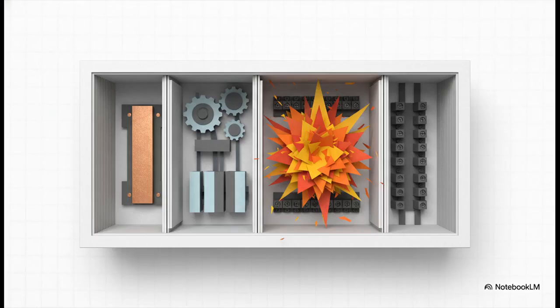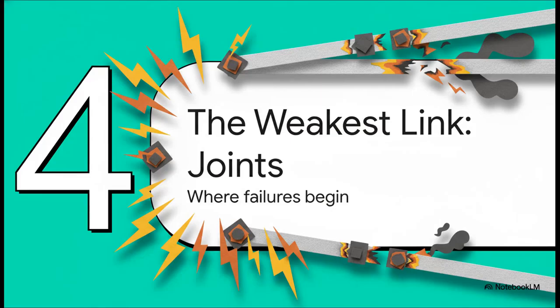Beyond just spacing the bars out, we also have to separate the compartments they sit in. Forms 1 through 4B describe this segregation. Form 4 separation isolates the bus bars, the functional units, and the terminals completely from each other. This radically improves safety for maintenance workers by preventing accidental contact with live parts, and it stops a localized arc flash from spreading like wildfire. But as you might guess, putting in all these physical barriers significantly adds to the panel's cost, its size, and the overall layout complexity. Which brings us to Section 4, the weakest link, joints, where most failures begin.